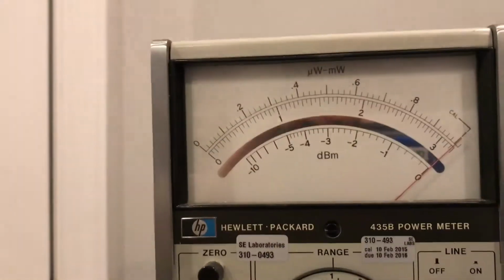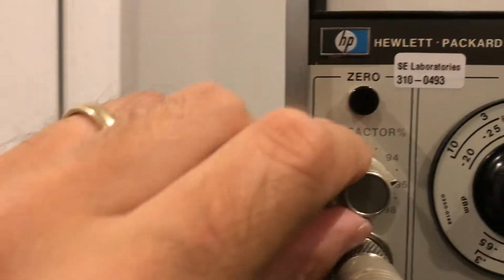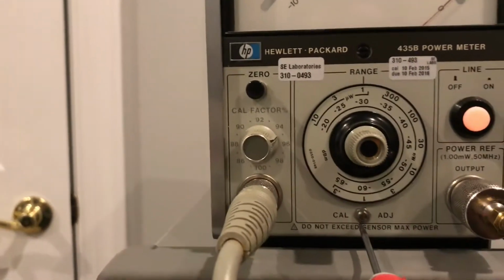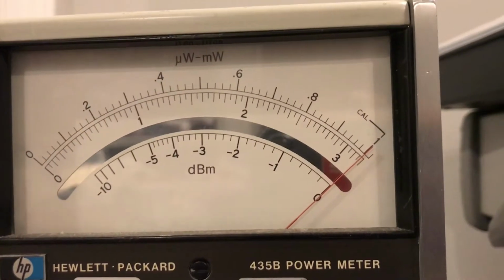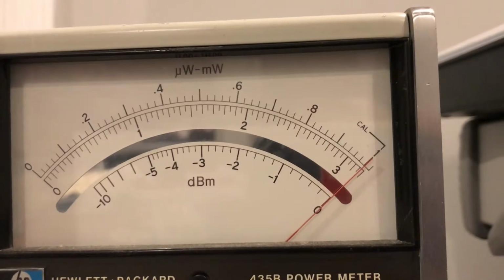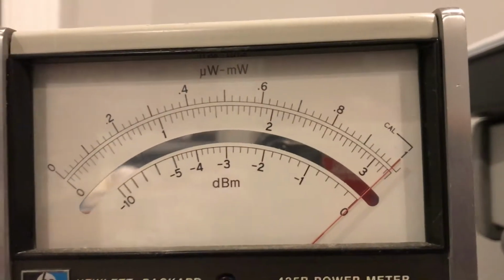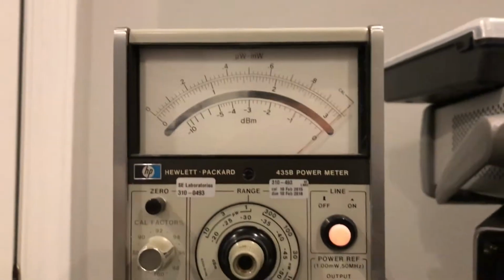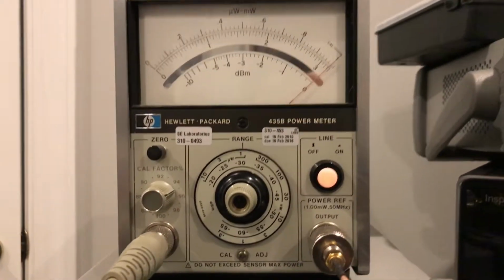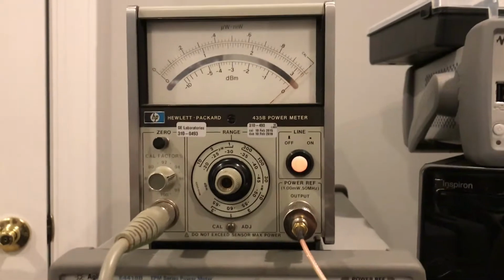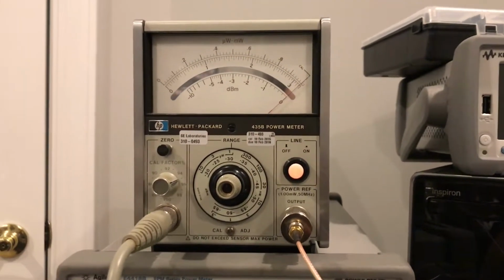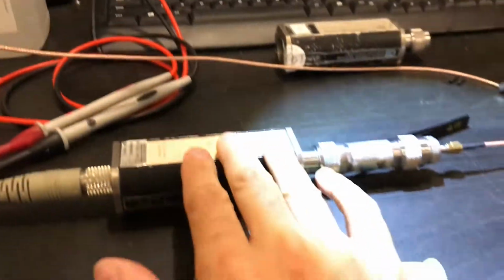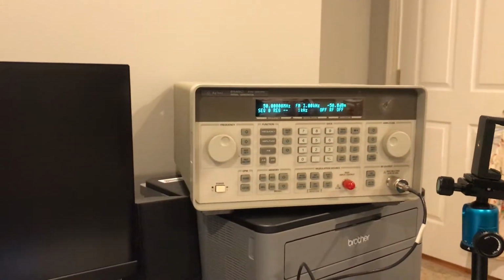So this sensor has a reference cal of 95, and our switch is set to 95, and we can very carefully adjust to get that just into cal right there. So using the 435B, it appears that the sensor is working. So what I'm going to do now is set this sensor up to the signal generator, and we'll run some tests using the signal generator.